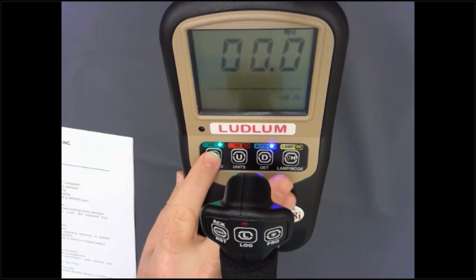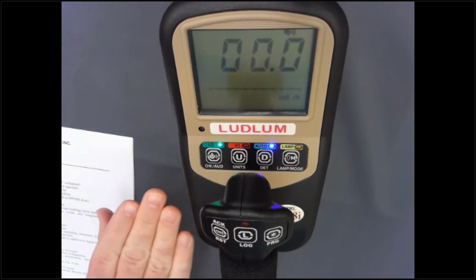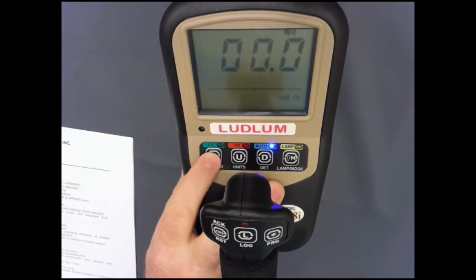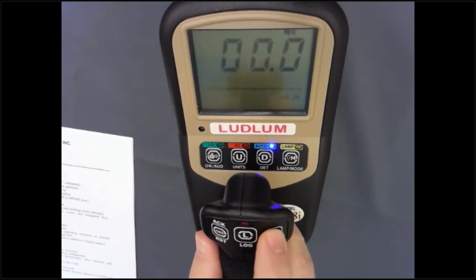I will not go through all the setup menu features because there are quite a lot, but I will show you how you can also get to the setup menu without having to turn the instrument off, and that's just by holding the on button for 2 seconds. And when it starts counting down, that resets the 4-second timer, and at that point we can go into the setup menu. So for the first 4 seconds, once you get to the rate screen, the program button gives you access to the setup menu. After 4 seconds, then you have direct access to the integrated dose that's on the internal detector, so long as you do have an internal detector.